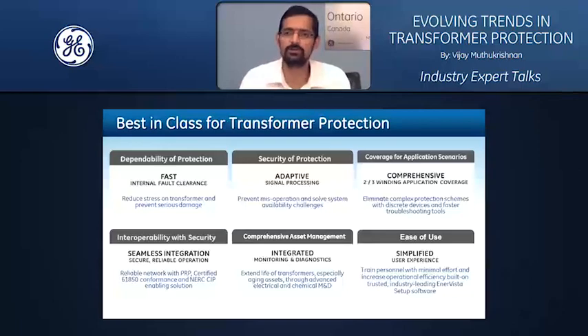The second dimension of reliability for a transformer protection relay is security of protection. You really don't want your transformer protection relay to operate when you don't want it to operate, for conditions such as through faults or external faults. So the relay has to have some adaptive signal processing capabilities to make that happen, so that you can avoid availability challenges on the transformer in the context of your system operation. These are the two aspects of reliability.